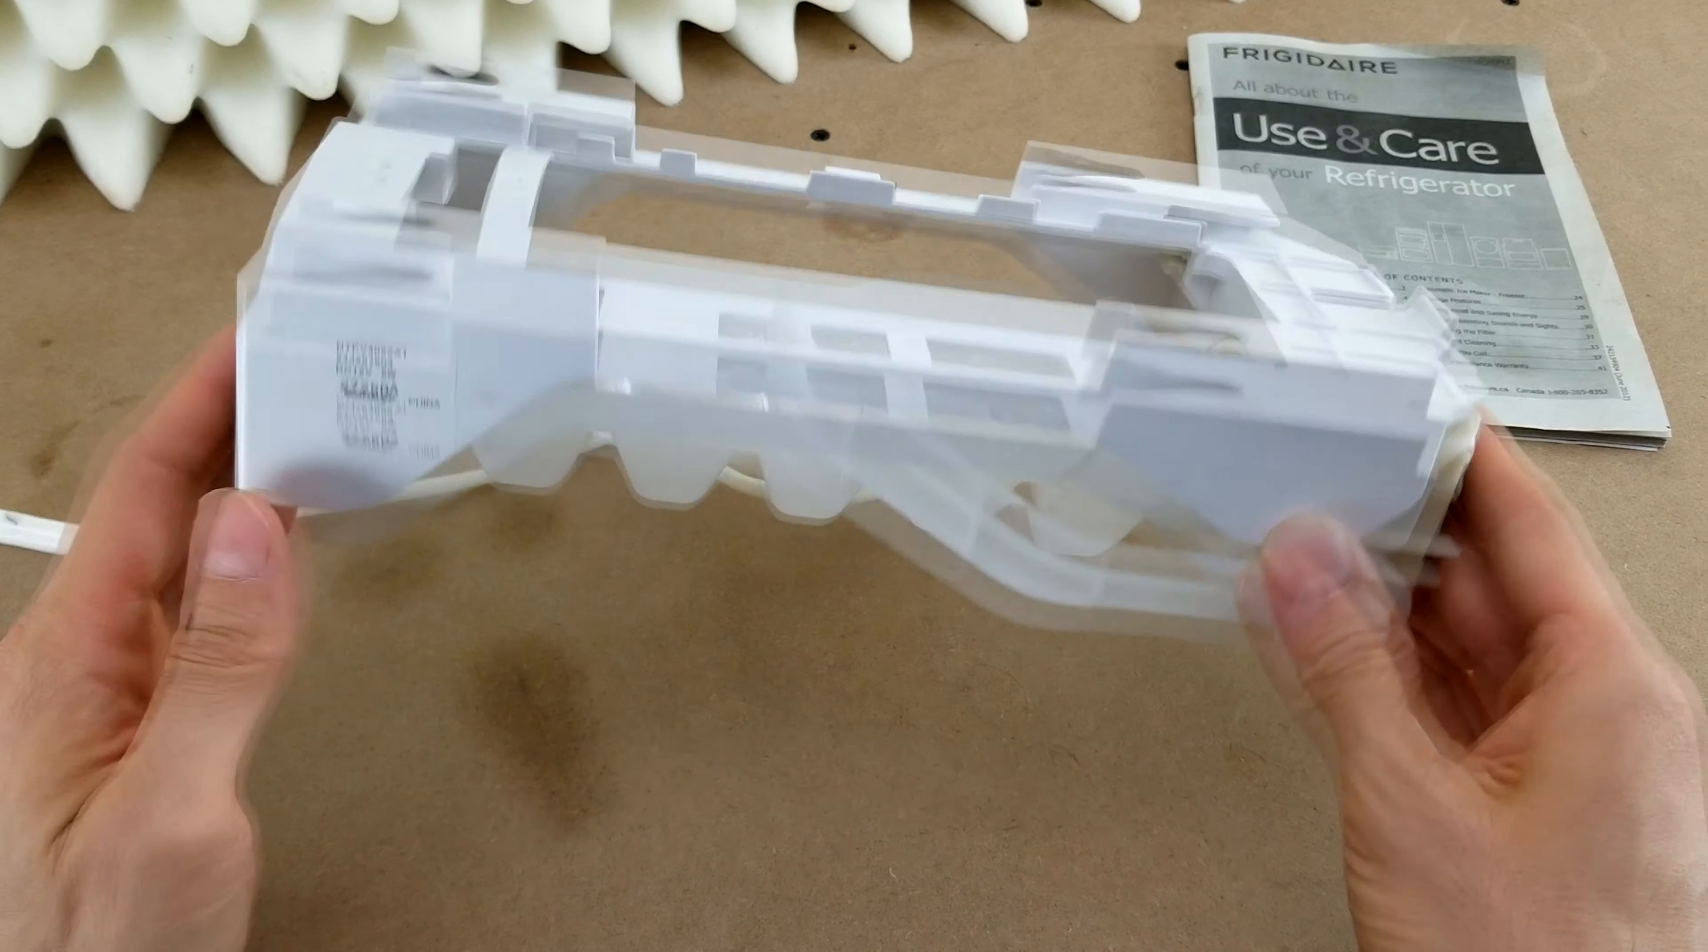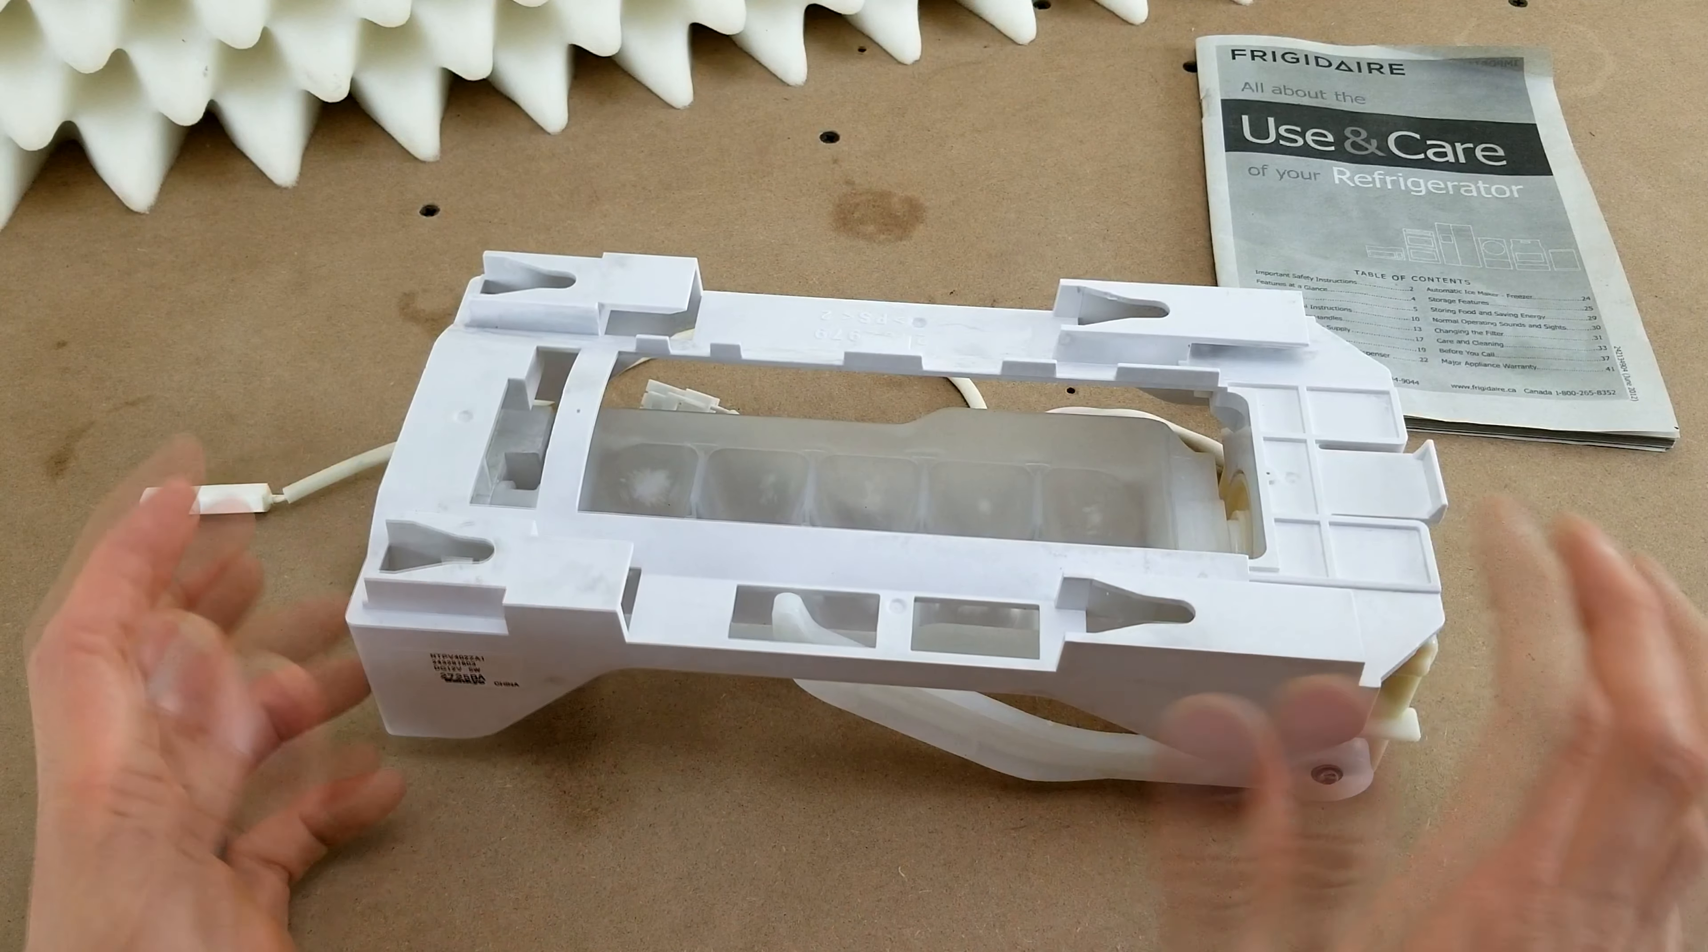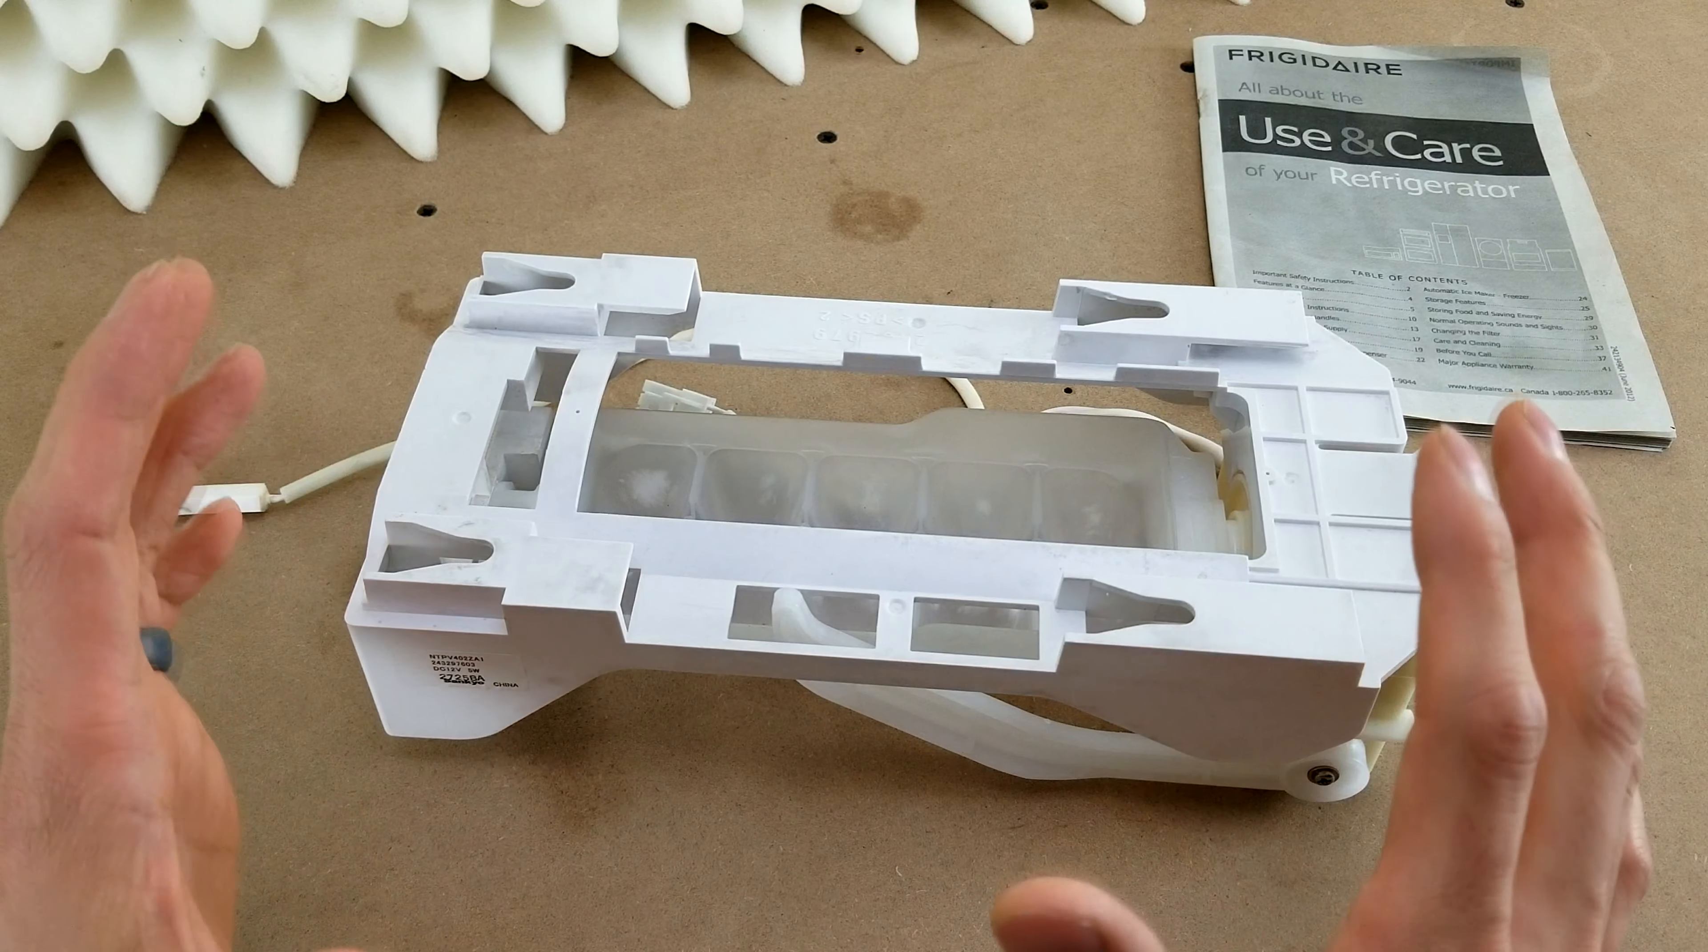If that doesn't fix it or you don't see an issue with the temperature sensor, the other problem you might be having is that the evaporator coil in the back of the ice maker section might be frozen solid into a big block of ice. If you look back there while you have this whole thing apart, you might be able to see that. Anyway, that's it as far as this goes. I just want to point you in the right direction if you're having the same issue as me. Good luck.